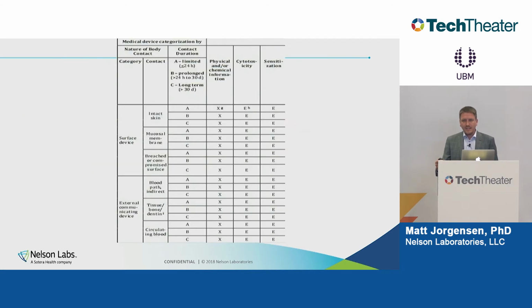The way this is manifested — from the new draft of ISO 10993-1, not out yet — you can see that rather than putting check boxes for all these different biological risks or endpoints like cytotoxicity and sensitization, instead of an X there, it's an E. That means rather than making it look like you always have to do those tests, it means you really just need to evaluate those. This is why it's more opened up. The one thing that's still an X, checked for everything, is material and chemical information.